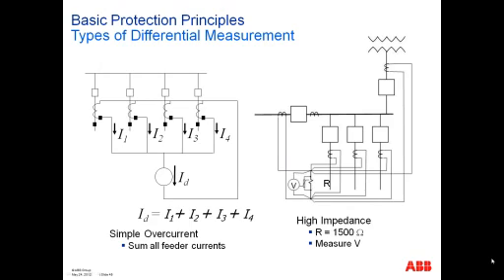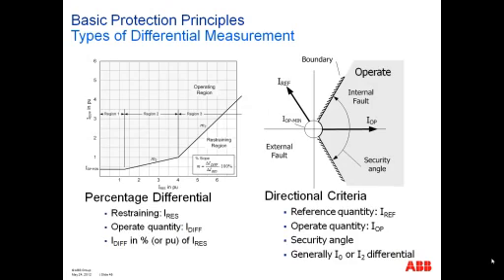And you have high impedance bus protection, and this is where you add up all the buses, the currents of all the buses, and you flow through a differential measurement. Normally, what goes into a bus must come out of a bus. So the summation of ID you see at the bottom, I1 plus I2 plus I3 plus I4, would typically be 0. But if there is a difference, that difference goes through a very large resistance, producing a very large voltage, which immediately picks up and provides very high speed, reliable bus protection, and this is referred to as high impedance bus protection.